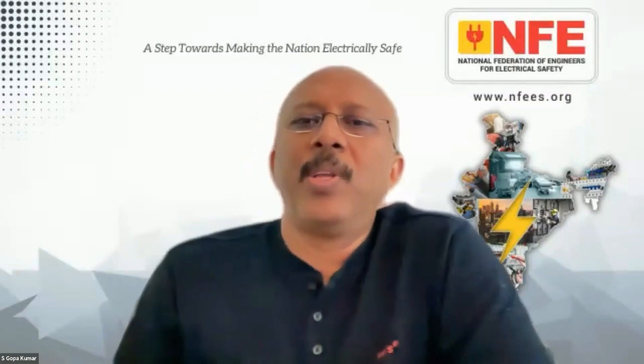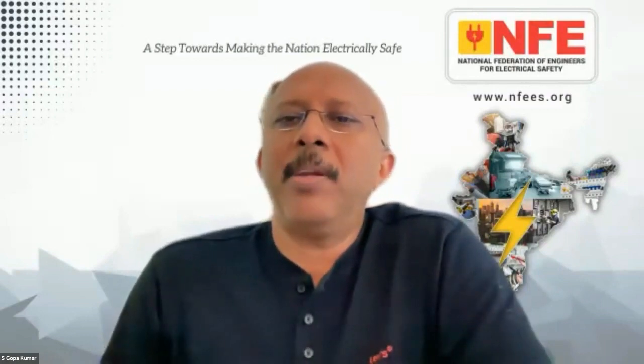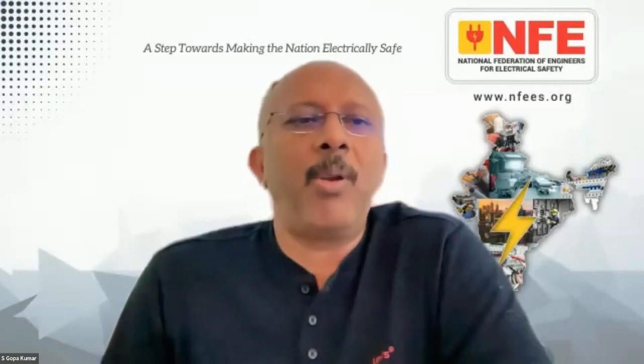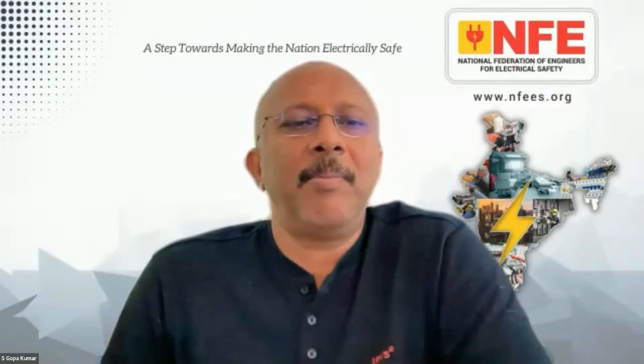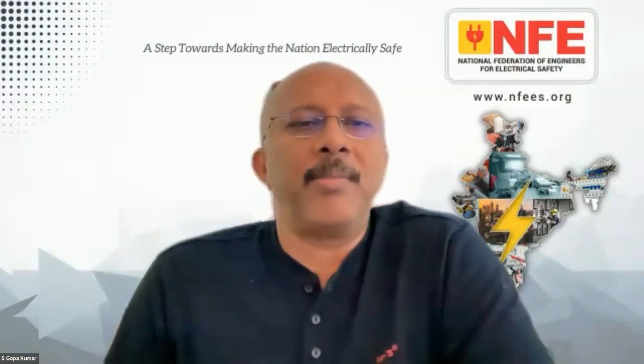Yeah. So thanks for the answer. The next question is: is it recommended to install an RCD as a mitigation if the fault loop impedance test fails? That means as a measure for fault protection. Yes, it is. However, there is a folly of our industry. So we got it wrong. We have this very terrible rule of the 1,667 ohms. You can allow 1,667 ohms if you have an RCD, but that still doesn't offer you any protection against fault currents. It's only earth leakage. So if you have 1,500 ohms, yes, if you have earth leakage, you can rely on your RCD. But if you have an overcurrent, you've got nothing still.